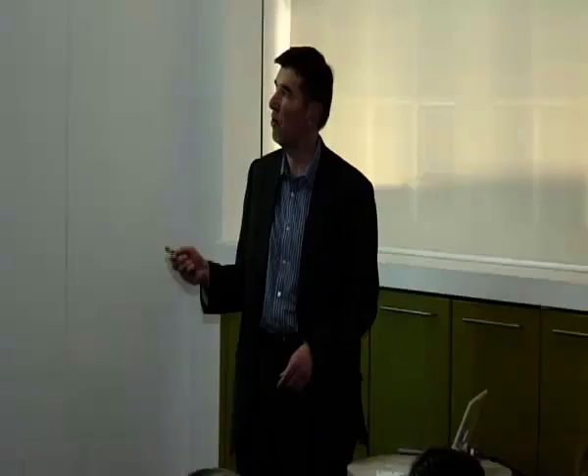On these elevations we're looking at protecting the facade with a tubular wraparound system. That tubular wraparound system needed some modelling to tell us how it would work and what the best configuration would be. What we came up with was circular tubes wrapped around the building. In some instances where we want to let more daylight in, these tubes have been flattened and the gap between them is greater. In other areas where the solar intensity is greater, the gap between the tubes is smaller and the tubes are wider. Another interesting thing we had to take on board in modelling this was the thought that desert winds could cause the building to act like a flute for most of the year - acoustic whistling all the time - and we had to model that as well to make sure that was addressed. So some quite complex things coming together here.